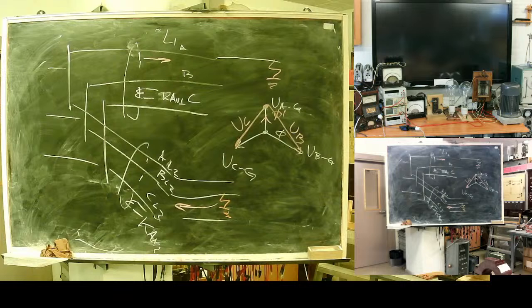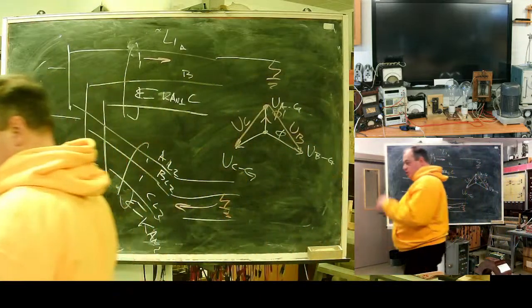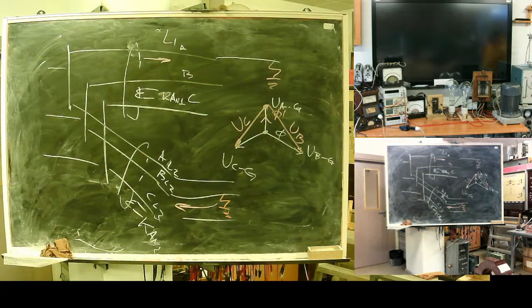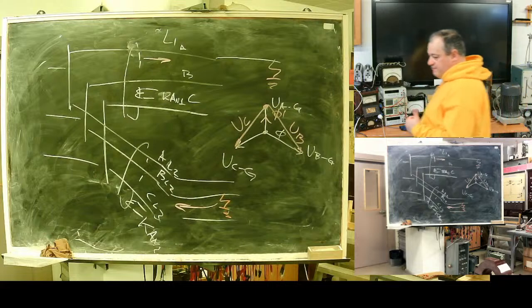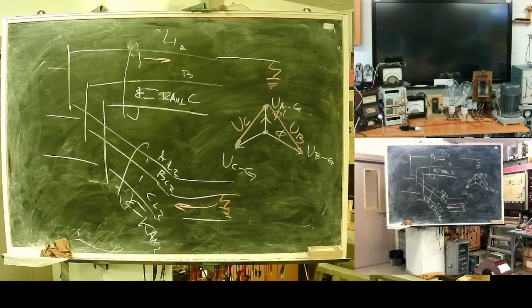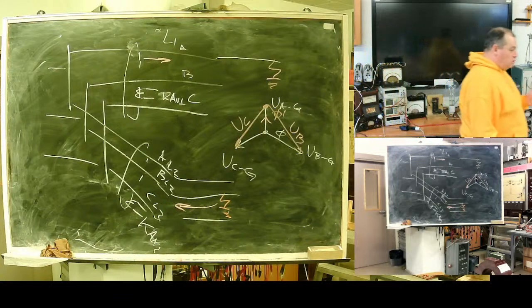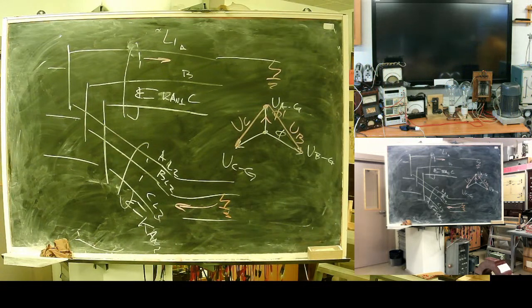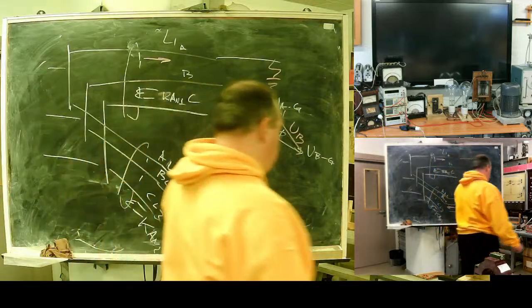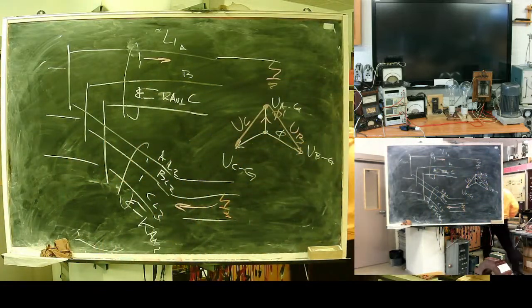So your relay should withstand this current. One of the problems of such earth fault protection, they are required to have very high overcurrent capability or resistance. In early version it was done with saturated transformer. In modern versions, special limiters in the input stage. Otherwise your relay will burn. Not every overcurrent relay is suitable for such kind of protection.